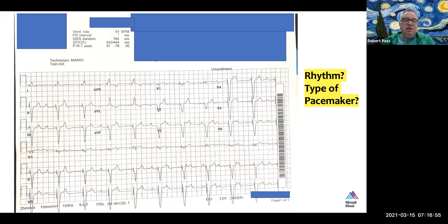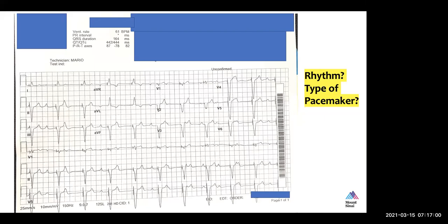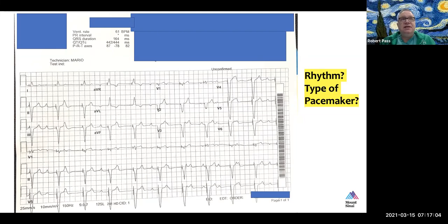We would not put permanent leads generally before post-op day 8 or 9. Studies have shown that up until that day, there's a reasonable chance of recovery, but after about day 8 or 9, the chance of recovery is below 5%. So that's the time we would normally put in a permanent pacemaker.